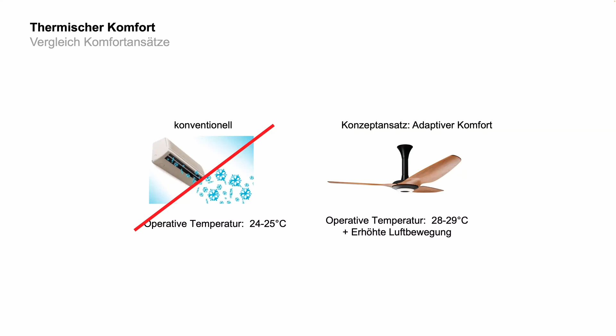This is the ASHRAE calculator of thermal comfort, and you have to be in that blue range. At 24 degrees with non-moving air, you're right in the center of comfort - it's all perfect, summer comfort is fine. If you're at 28 degrees and move the air by about 0.8 meters per second, you feel the same, although you have 4 degrees more in the room. So that principle allows us to reduce the amount of air conditioning because people feel the same and you don't need to cool the space as much as before.